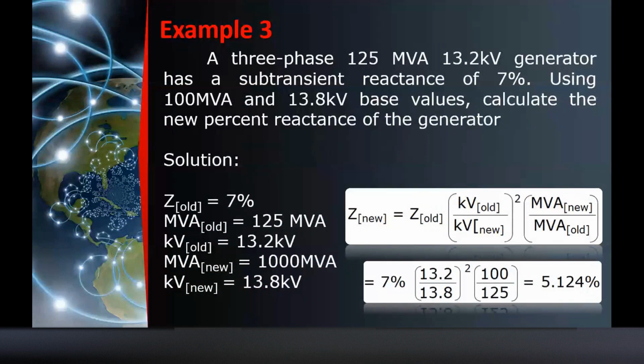So this is what I mean by very useful. For example, your motor is 380 volts and you connect it to 400 volts. Definitely the impedance of the motor at 380 is different from the impedance when you connect it at 400. That is also the concept of per unit. For example, a 3-phase 125 MVA 13.2 kV generator has a subtransient reactance of 7%. So that 7% is based on the 13.2 kV, which is the old impedance, okay?